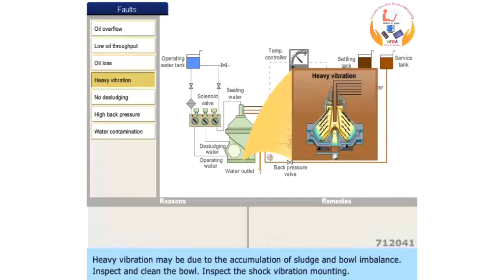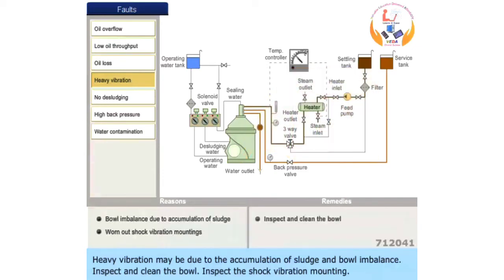Heavy vibration may be due to the accumulation of sludge and bowl imbalance. Inspect and clean the bowl. Inspect the shock vibration mounting.